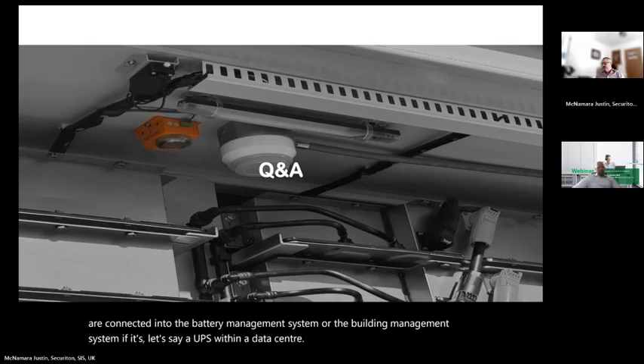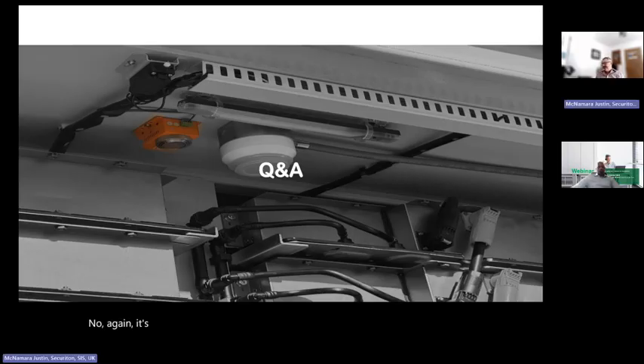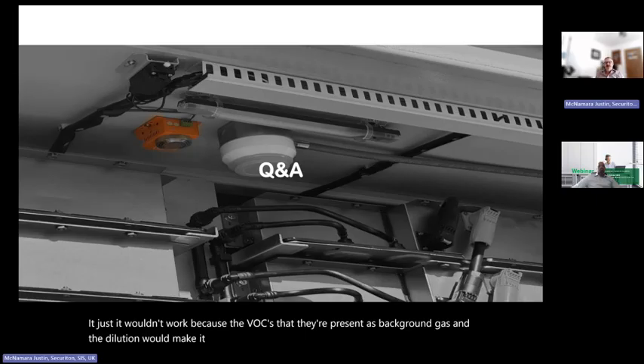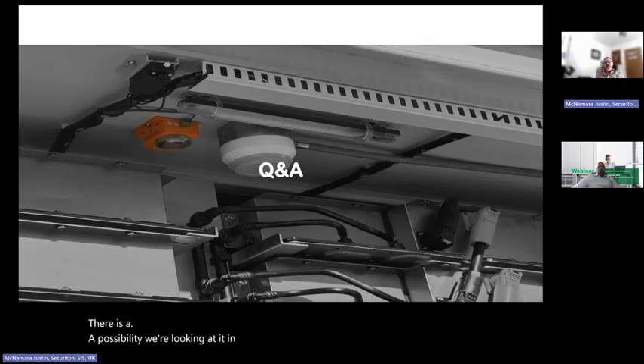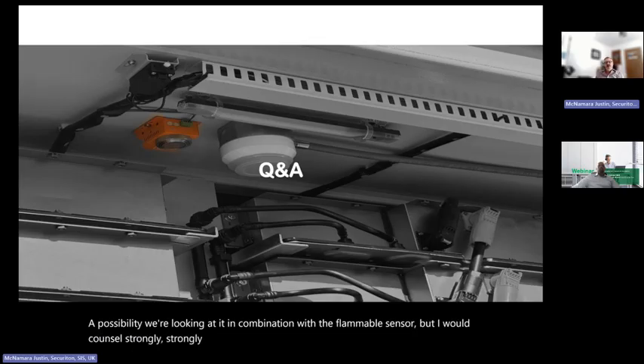Good. And the last question, Justin, is, can we integrate VOC detection directly with an ASD? No. Again, it's the short answer. The off-gas detection wouldn't work, because the VOCs are present as background gas, and the dilution would make it undetectable, or at least undetectable to be reliable. There is a possibility, we're looking at it in combination with the flammable sensor, but I would counsel strongly against incorporating VOC sensing into any ASD.